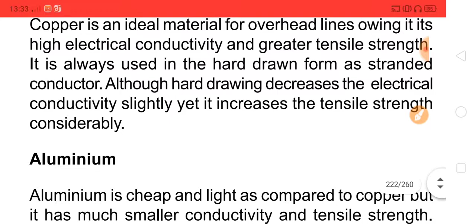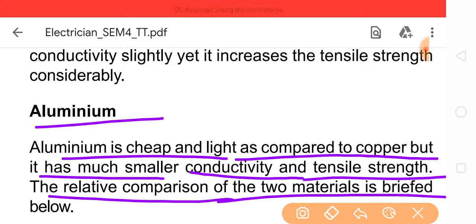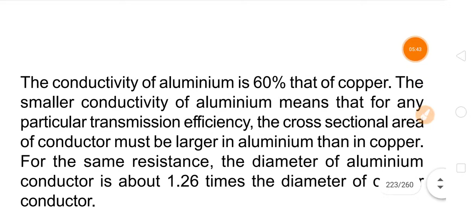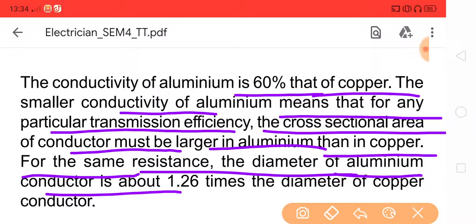Aluminium. Aluminium is cheap and light compared to copper, but it has a much smaller conductivity and tensile strength. The relative comparison of the two materials is briefed below. The conductivity of aluminium is 60% that of copper. The smaller conductivity of aluminium means that for any particular transmission efficiency, the cross sectional area of the conductor must be larger in aluminium than in copper. For the same resistance, the diameter of the aluminium conductor is about 1.26 times the diameter of the copper conductor.